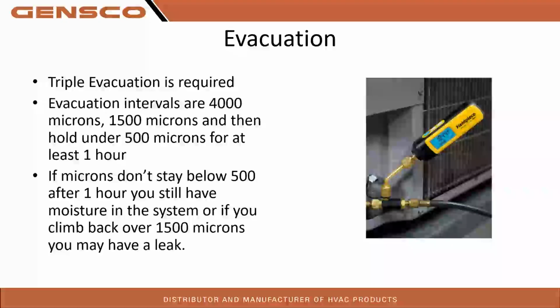So to do that triple evac, the expectation from Mitsubishi is you hook your vacuum gauge up to the system or your vacuum pump, and you pull it down with your micron gauge down to 4,000 microns. Once you hit 4,000, you break that vacuum with just dry nitrogen. Do not open it back up to the atmosphere because you're just introducing moisture back to the system. We don't want to do that. So just bring the pressure back up to 0 psi, just atmospheric pressure, with dry nitrogen only.